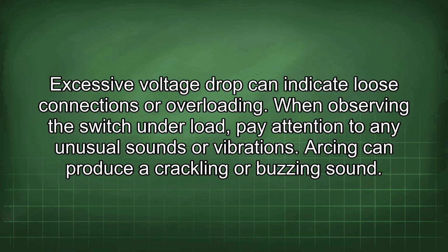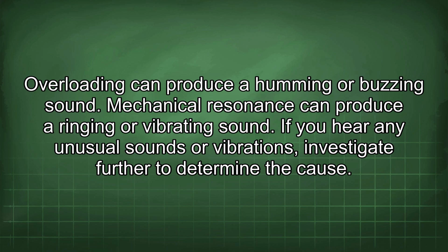When observing the switch under load, pay attention to any unusual sounds or vibrations. Arcing can produce a crackling or buzzing sound. Overloading can produce a humming or buzzing sound. Mechanical resonance can produce a ringing or vibrating sound. If you hear any unusual sounds or vibrations, investigate further to determine the cause.